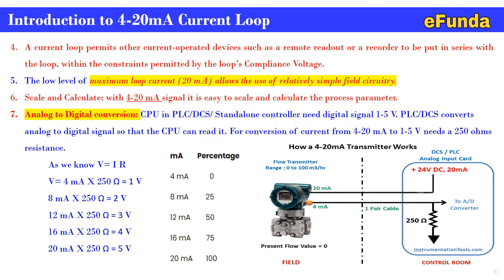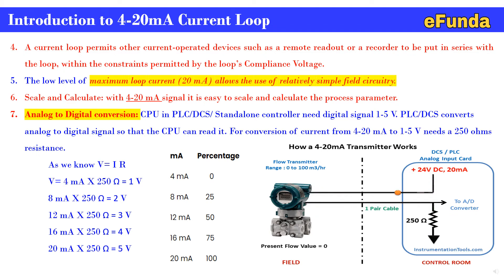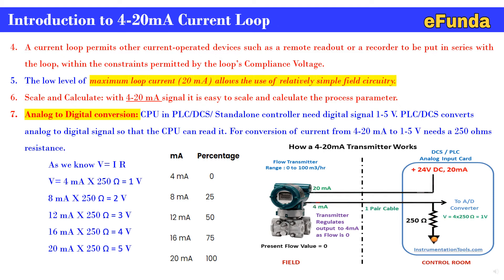For further understanding, one can refer to the table where current and percentage are populated: 4 milliamp is 0%, 8 milliamp is 25%, 12 milliamp is 50%, 16 milliamp is 75%, and 20 milliamp is 100%. This is how the 0 to 100% range is calibrated in terms of milliamp, with the current transferred to the control room and converted to the required voltage using a 250 ohm resistor for DCS, PLC, or standalone controller.